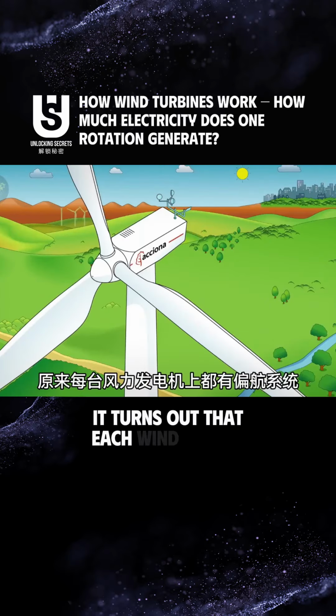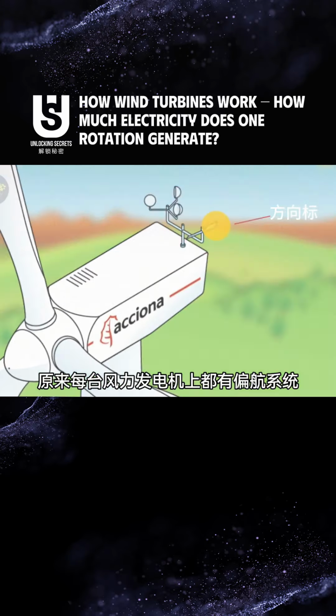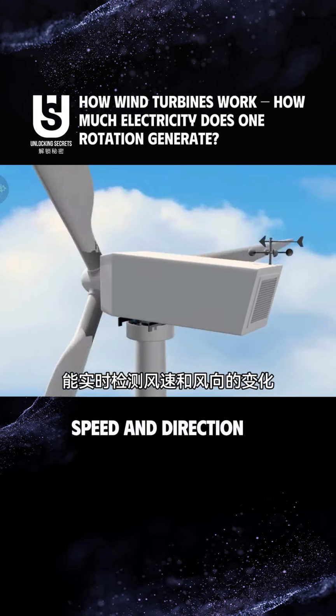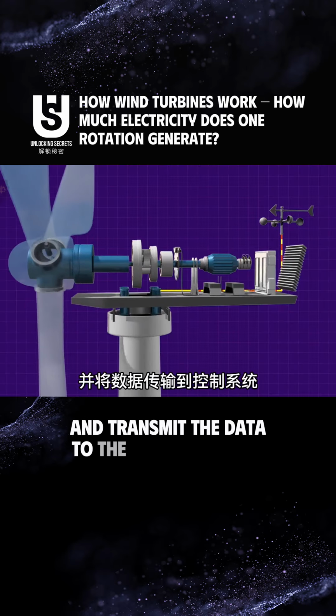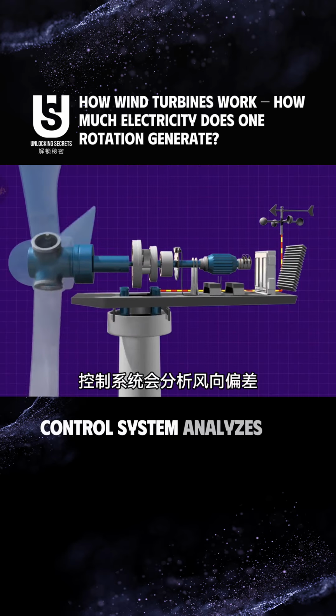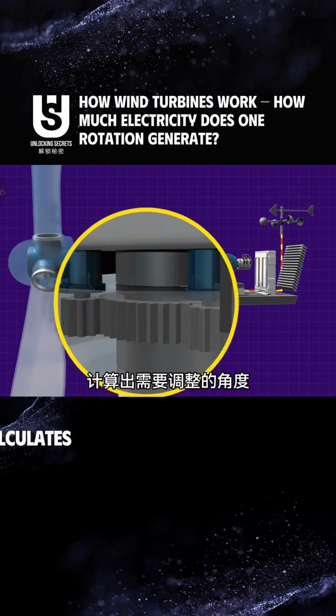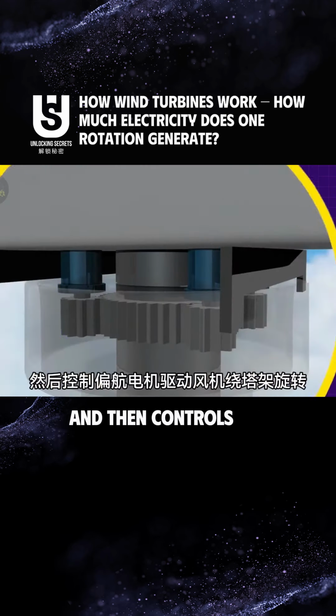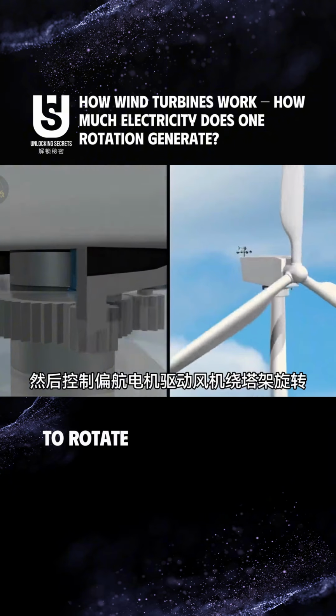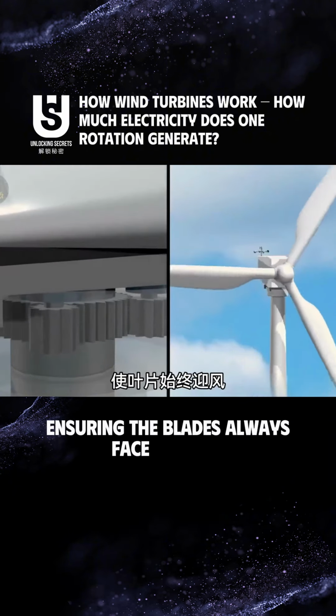It turns out that each wind turbine is equipped with a yaw system, which can detect changes in wind speed and direction in real time and transmit the data to the control system. The control system analyzes the wind direction deviation, calculates the necessary adjustment angle, and then controls the yaw motor to drive the turbine to rotate around the tower, ensuring the blades always face the wind.